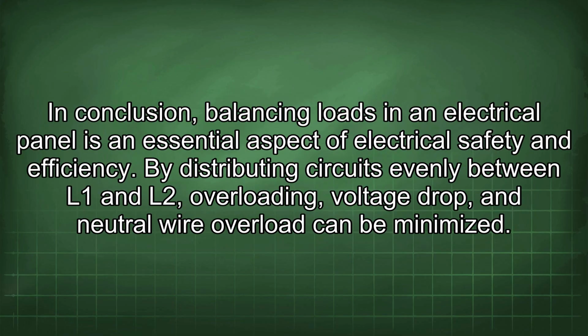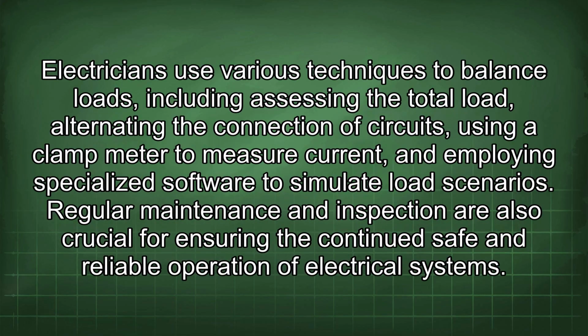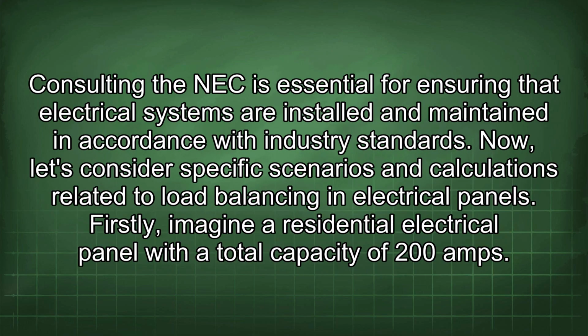In conclusion, balancing loads in an electrical panel is an essential aspect of electrical safety and efficiency. By distributing circuits evenly between L1 and L2, overloading, voltage drop, and neutral wire overload can be minimized. Electricians use various techniques to balance loads, including assessing the total load, alternating the connection of circuits, using a clamp meter to measure current, and employing specialized software to simulate load scenarios. Regular maintenance and inspection are also crucial for ensuring the continued safe and reliable operation of electrical systems. Consulting the NEC is essential for ensuring that electrical systems are installed and maintained in accordance with industry standards.